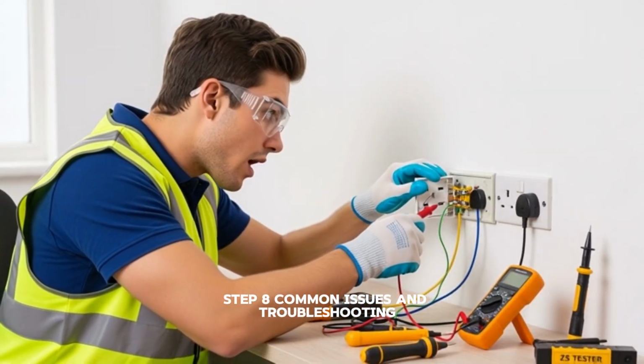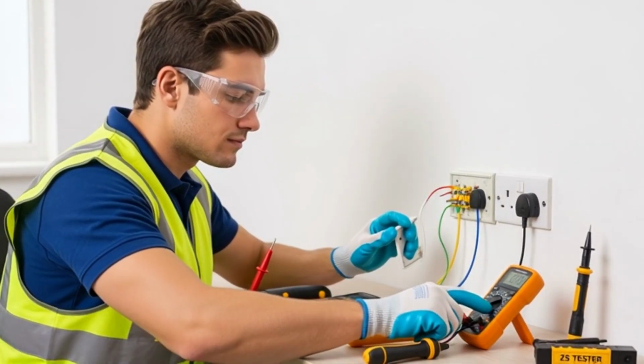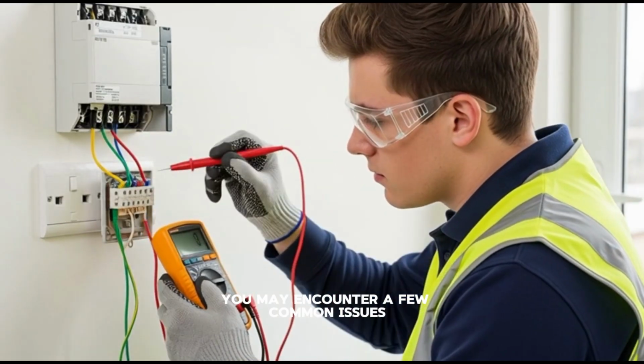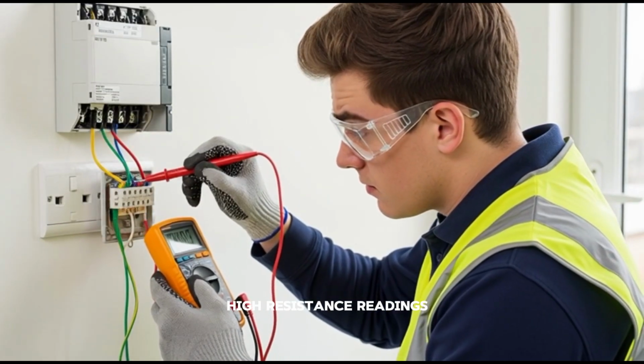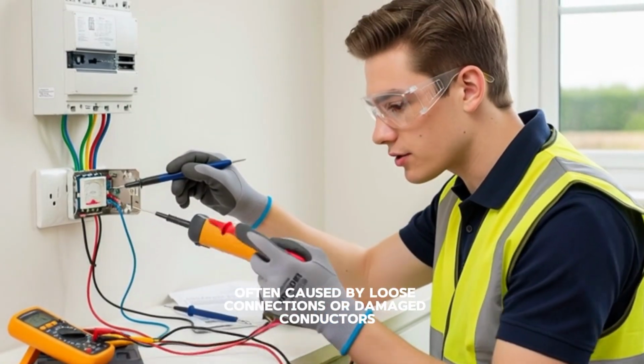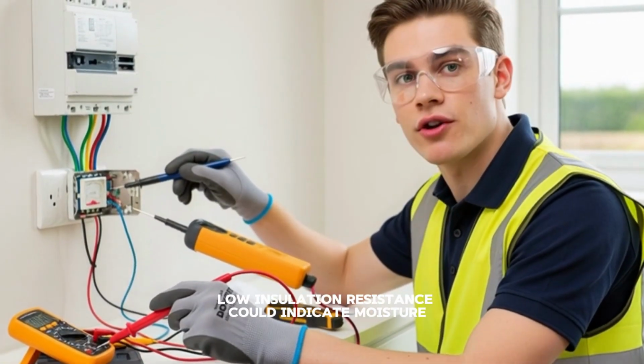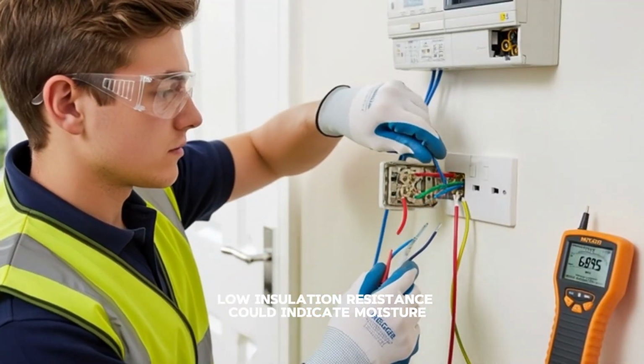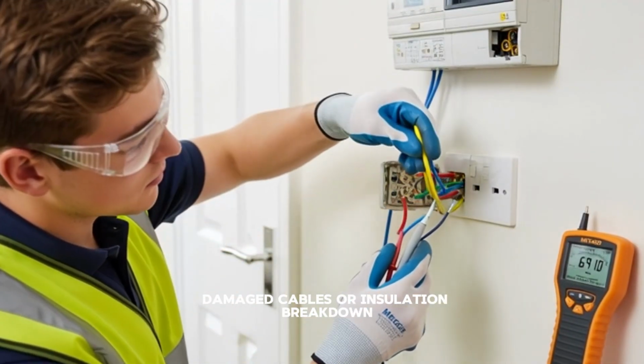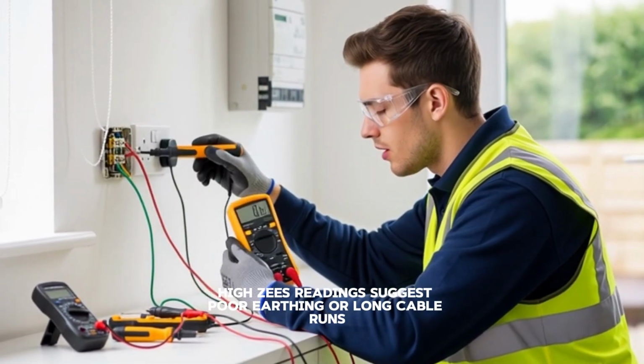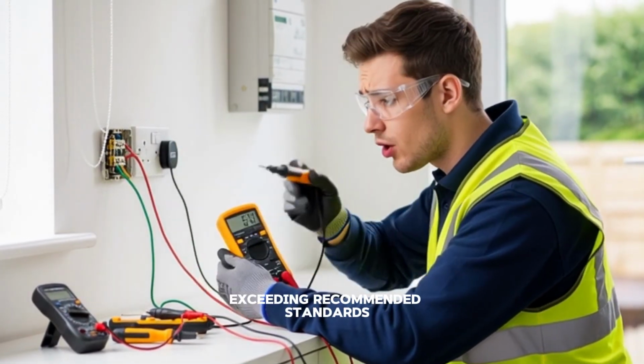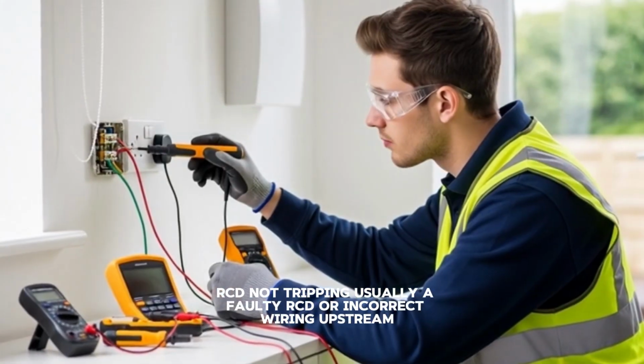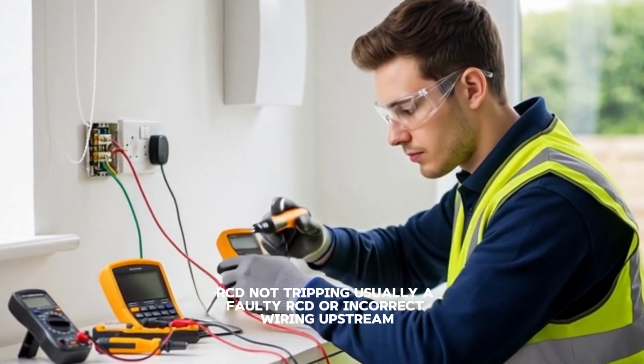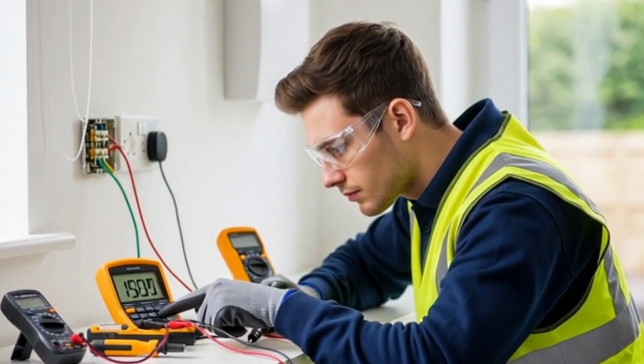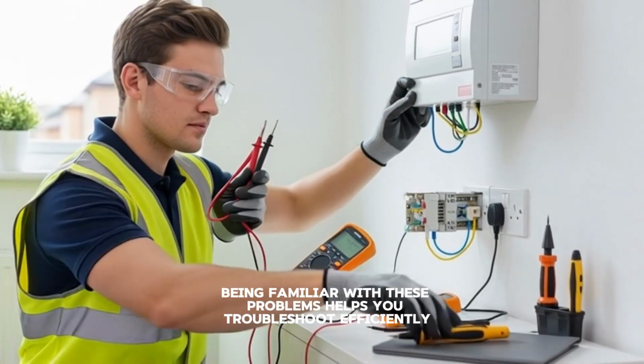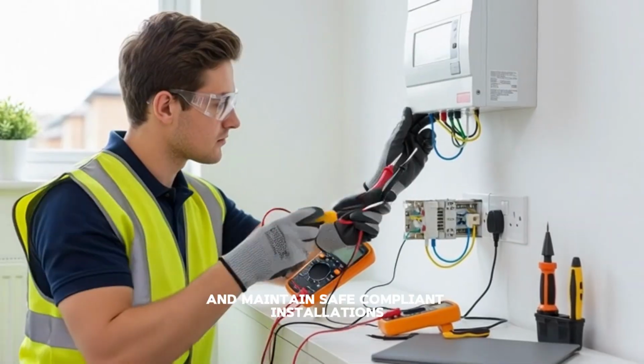Step 8. Common issues and troubleshooting. While testing ring circuits, you may encounter a few common issues. High resistance readings, often caused by loose connections or damaged conductors. Low insulation resistance could indicate moisture, damaged cables, or insulation breakdown. High Zs readings suggest poor earthing or long cable runs exceeding recommended standards. RCD not tripping, usually a faulty RCD or incorrect wiring upstream. Being familiar with these problems helps you troubleshoot efficiently and maintain safe, compliant installations.